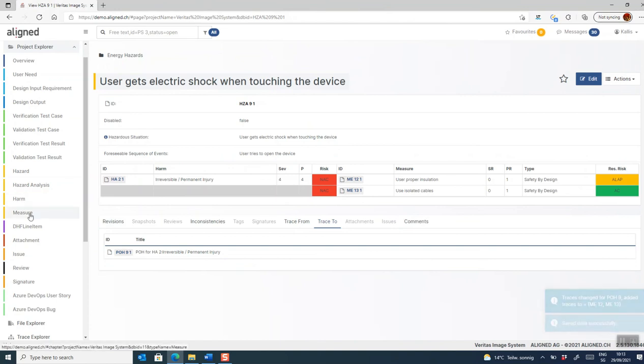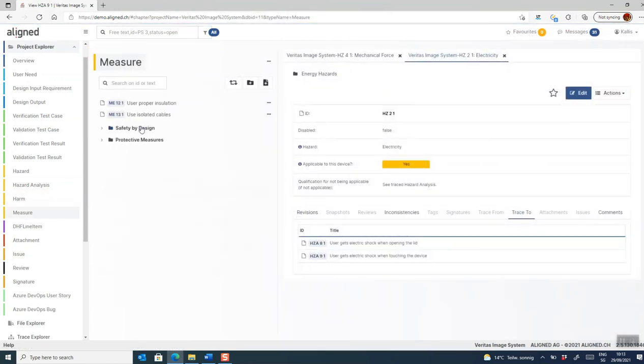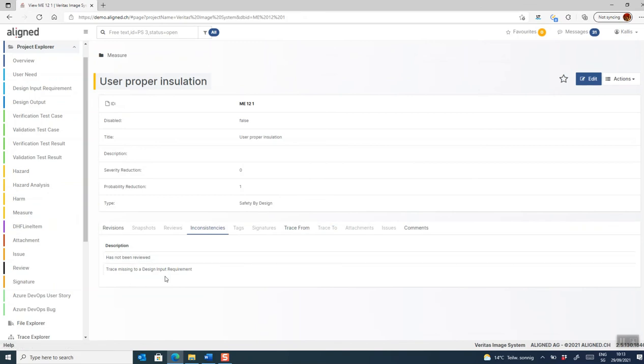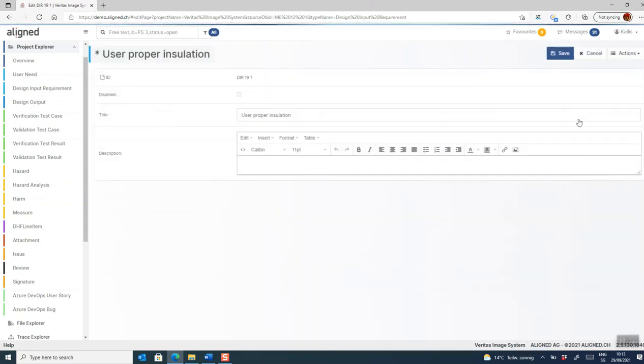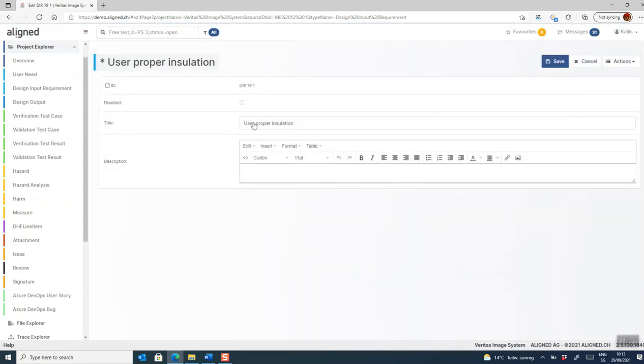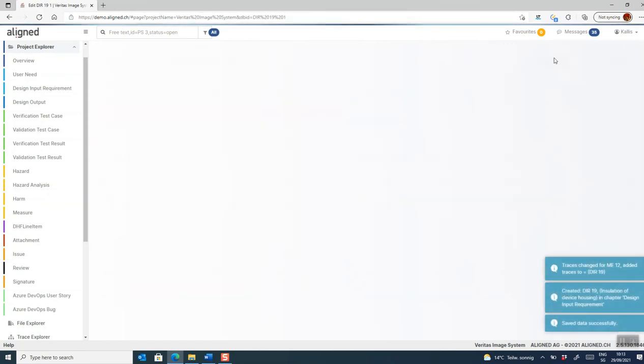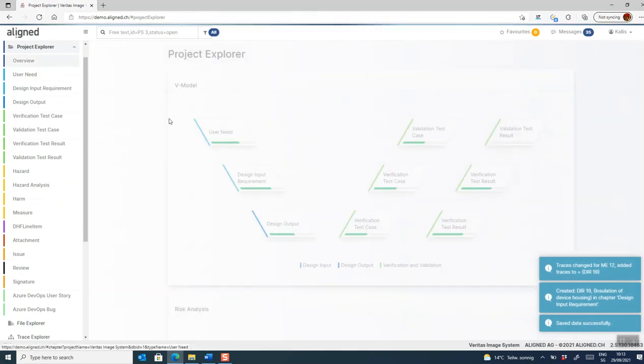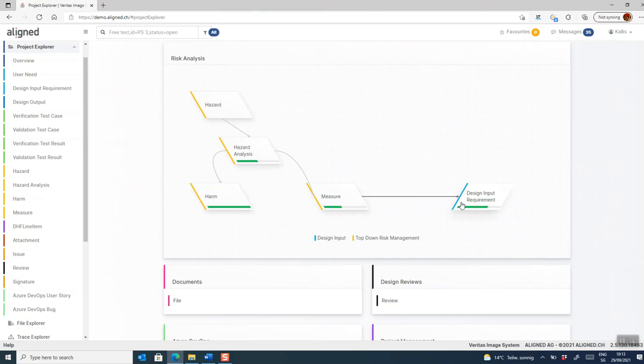We can go and take a look at our measures. So these are the two measures that I just added. And if we open one of them, the inconsistencies will tell us that it lacks a trace to a design input requirement. So it indicates that although we have recorded the mitigation, it's not yet implemented. So let's create a new requirement for this measure. And with this way, we can use our risk assessment to drive the design of our medical device.